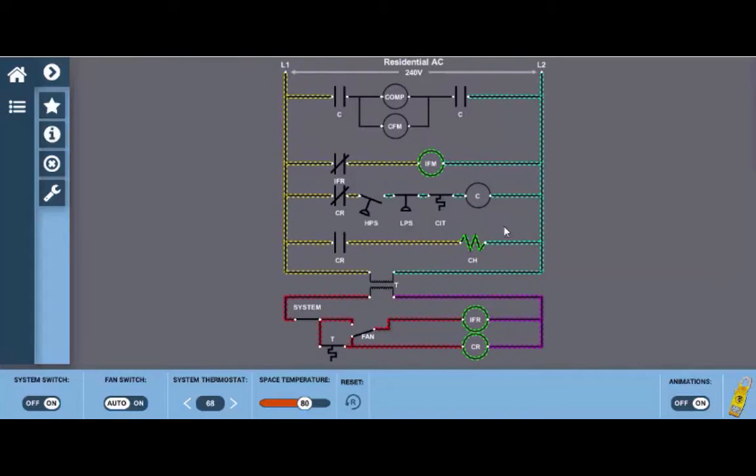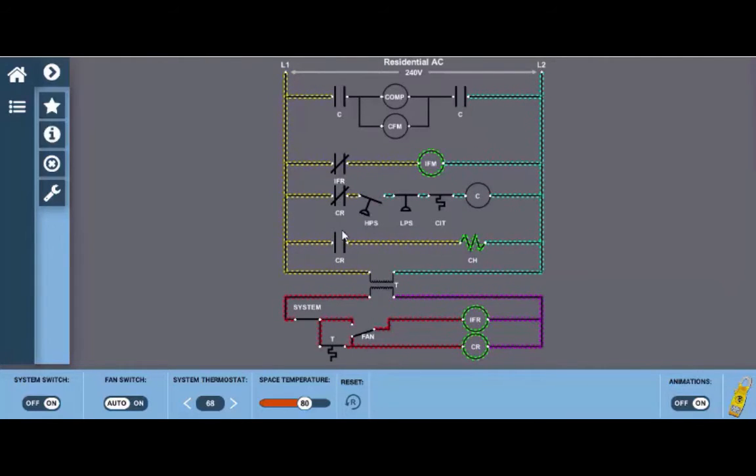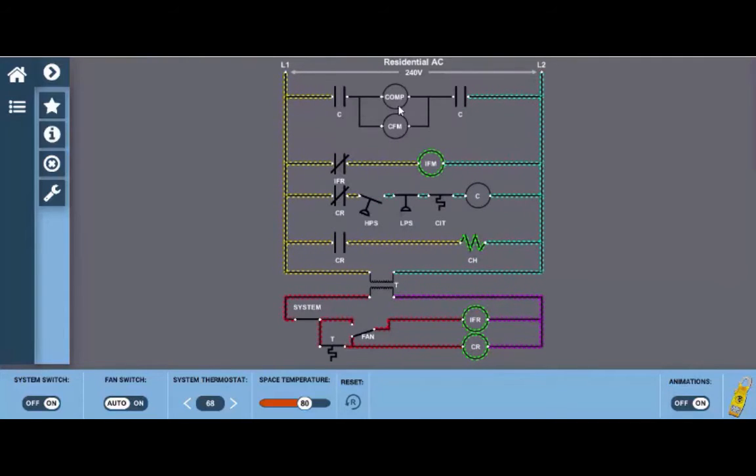Now this could lead us to a lot of possible causes not knowing what the problem is. It could be possibly the CR relay is bad. It is possible that we have a faulty set of CR contacts here, that we have one of the safety switches is at fault, or possibly the contactor coil itself or its contacts are at fault.